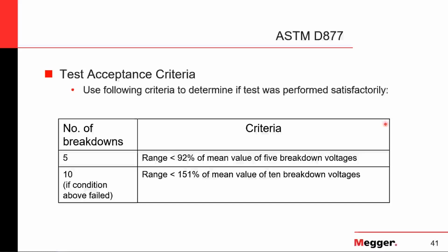And on that part, we're going to look again to ASTM D3487 as well as IEEE C57.106. In the ASTM standard, we will have limits for received new oil and new processed oil. So remember, ASTM D877 is only going to give us a recommendation for received new oil. And for ASTM D1816, we have values for both of the settings depending on the gap we are using.